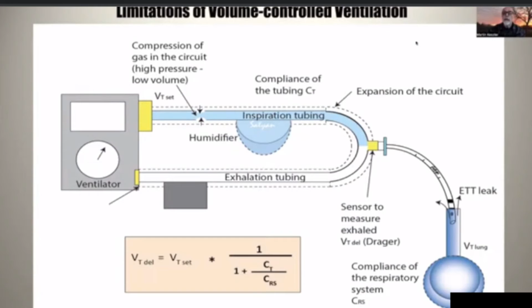There will always be some loss of volume to compression of gas within the tubing, stretching of the tubing, and of course compression within the humidifier as well. But in neonates with uncuffed endotracheal tubes, we also have variable loss of tidal volume to endotracheal tube leak. And as a consequence, the amount of gas that actually enters the patient's lungs is only very loosely related to the set tidal volume, especially when the lungs are very small relative to the volume and compliance of this circuit. So for that reason, we all adopted pressure-controlled ventilation and have used it for many years.